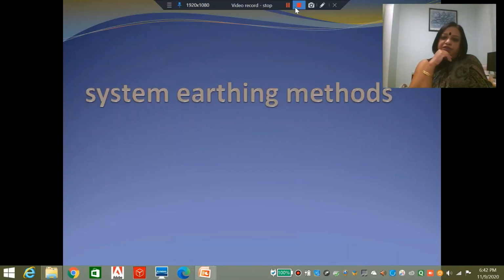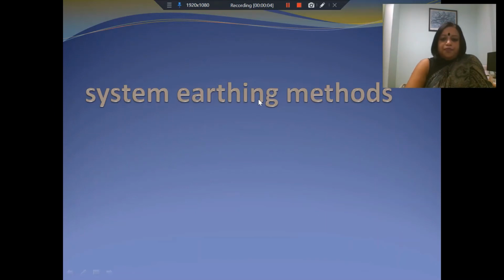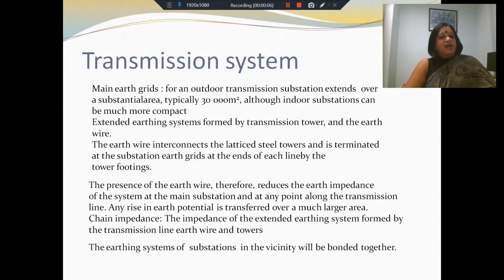So in this respect, first we will talk about system earthing methods. Now, when we have a transmission system, the transmission system takes a very large area. It extends over a very large area, especially when you have an outdoor transmission system. Typically, they have an area of 30,000 meters square, and this requires a main earth grid. The main earth grid is where you have a grid which is connected at several points to ground.